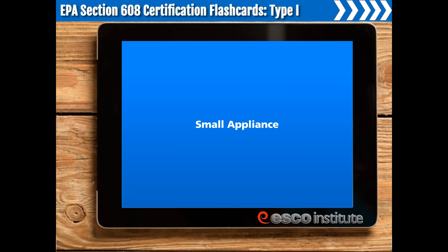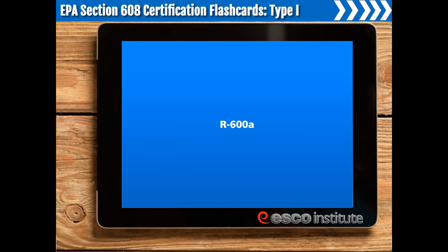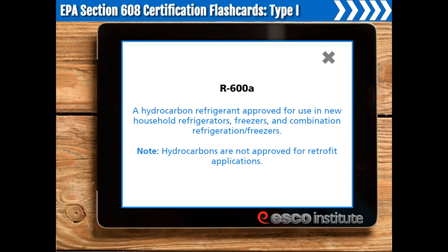Small Appliance. Products manufactured, fully charged, and hermetically sealed in a factory with five pounds or less of refrigerant. When servicing a small appliance, it is not mandatory to repair a leak, but it is recommended to do so whenever possible. Technicians servicing small appliances must have Type 1 or Universal Certification. R600A is a hydrocarbon refrigerant approved for use in new household refrigerators, freezers, and combination refrigeration freezers. Note: hydrocarbons are not approved for retrofit applications.